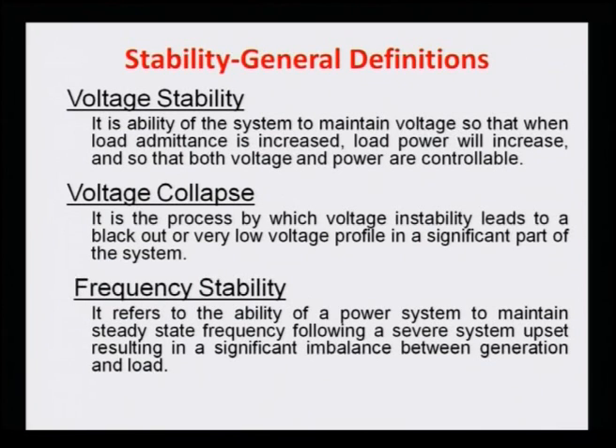Frequency stability refers to the ability of a power system to maintain steady state frequency following a severe system upset, resulting in a significant imbalance between generation and load. If there is a load mismatch, the frequency of the system will change, because the difference between power drawn and power input/output is either gained or lost as kinetic energy. Whenever there is a gain or loss in kinetic energy, the frequency of the system changes.